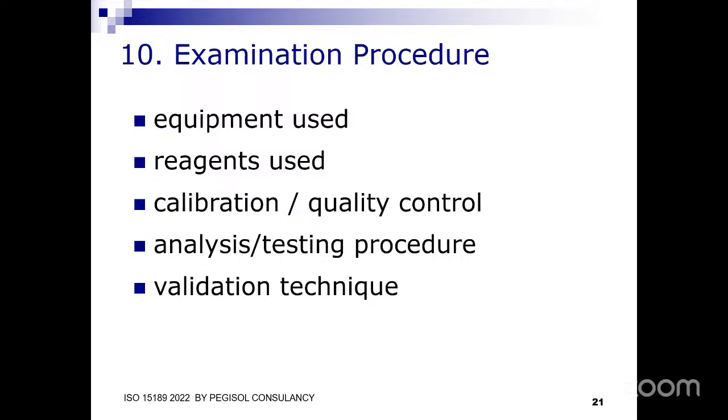And now you want to start doing HIV viral load, you want to start doing Lassa fever. You can't just go and buy kits and say, oh, because we have been using this equipment to run other tests. You have to validate that new test on that equipment before you start using it.